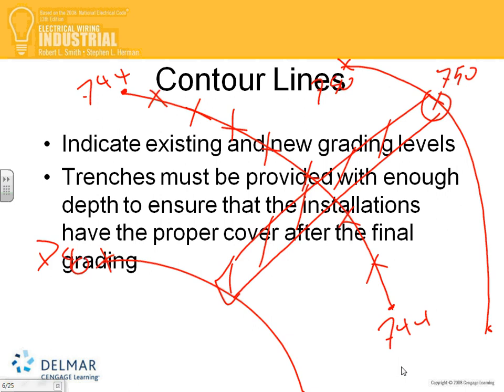So we start at 0 here. If we start at 0 feet here, I'm going to end up going up here. I'm going down, I'm going to end up down. My conduit at the same location is going to be 10 feet down or 10 feet up. So if I start at 0, going 10 feet up in the air - can you guys see that? Because if you start at the same elevation, 0, your conduit is going to go up in the air 10 feet. So these are things you have to pay attention to, because the elevation is going down this way. Any question, guys? That's the only place where the contour line becomes a big deal, really, for us - conduit trenching, when we trench.